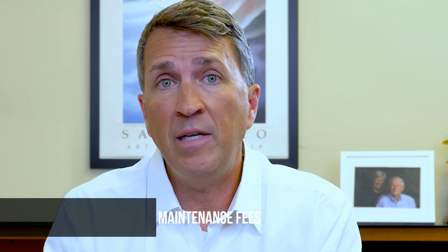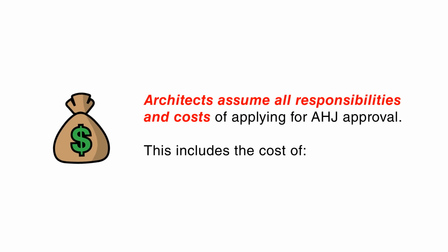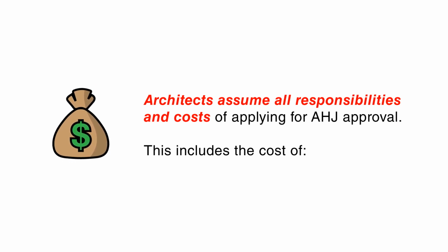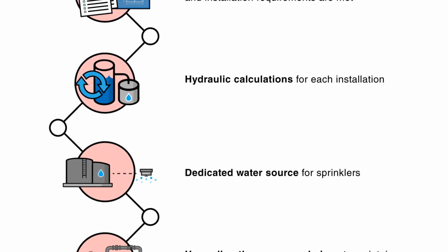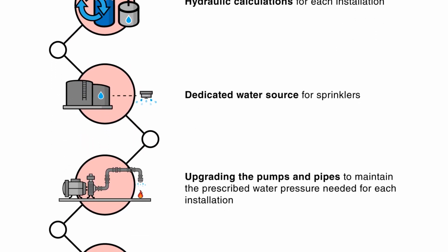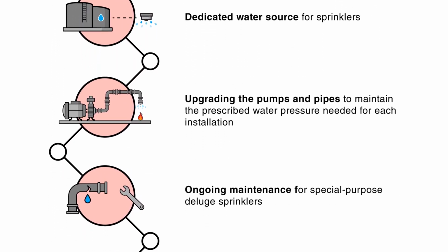There are hidden costs and maintenance fees associated with special purpose deluge sprinkler systems that do not exist with fire resistive assemblies. When you factor in the architect's time to prepare the technical data required for submission to the AHJ, as well as the specific requirements needed for this alternate system, it becomes more expensive than fire resistive glass assemblies.